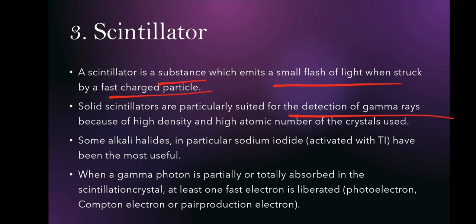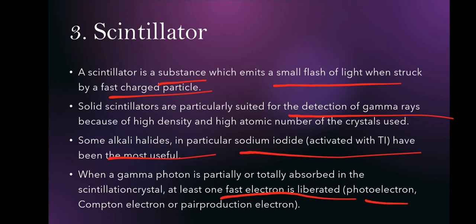Some alkali halides, in particular sodium iodide, have been the most useful. Sodium iodide activated by Tl is usually used as a scintillator. When a gamma photon is partially or totally absorbed in the scintillation crystal, at least one fast electron is liberated. This electron can be a photoelectron, a Compton electron, or a pair production electron.